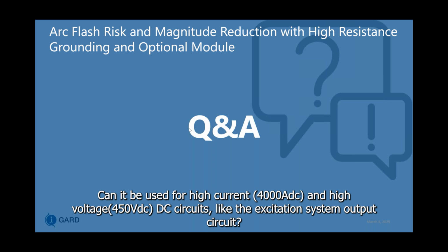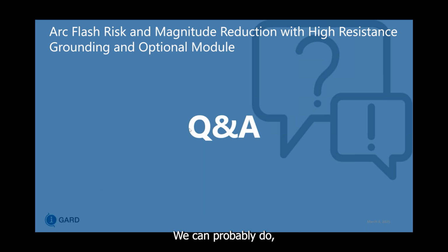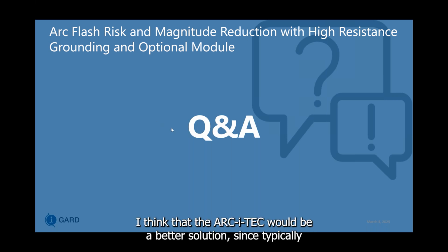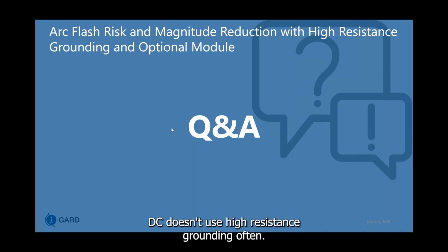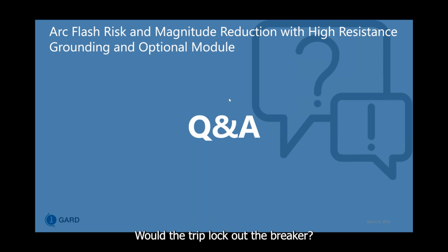Can it be used for high current 4000 amp DC and high voltage 450 DC on DC circuits like the excitation system output circuit? We can probably do the DC based variants with the ARC-i-TEC unit, which is the combination of using an ARC relay that has both current and light and pressure sensors. For 4000 amps DC, yeah, I think that the ARC-i-TEC would be a better solution since typically DC doesn't use high resistance grounding often.